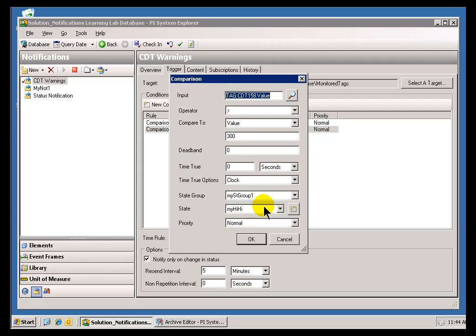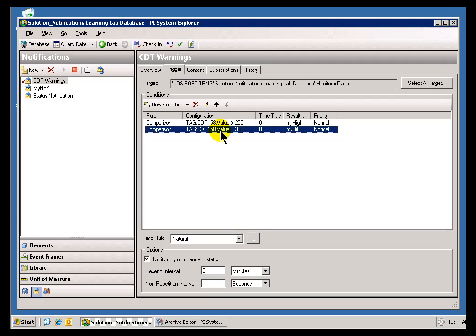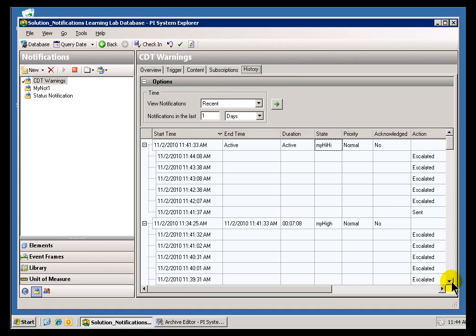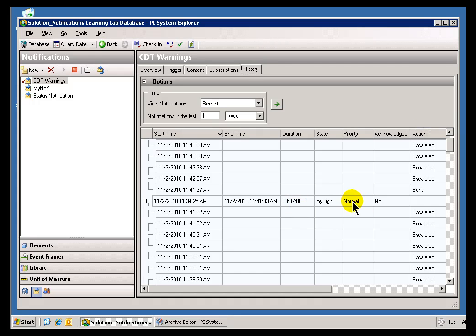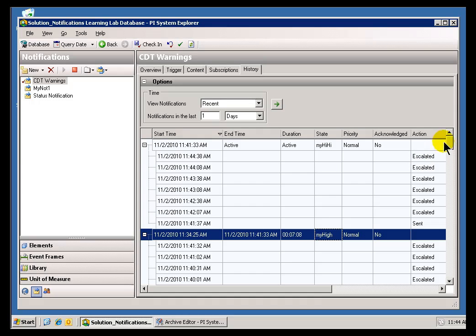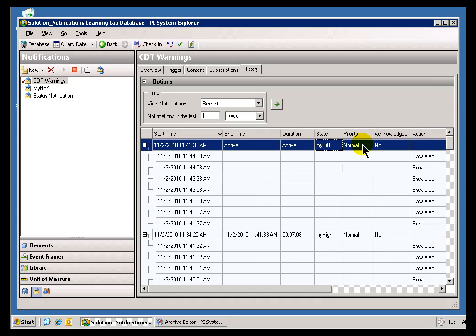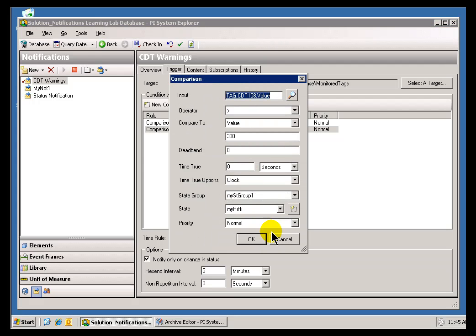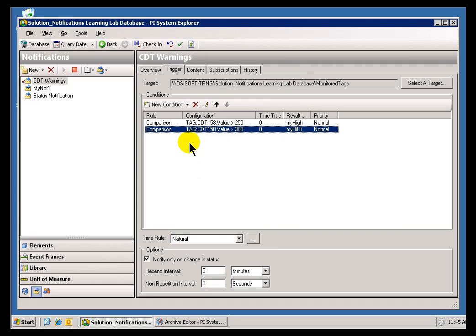Now if you look at this next one, when it's greater than 300, we're going to say that's a High High Alarm, or High High Notification — reflective of something in a more severe State. That's going to show up when you look at the History. I drove that Tag to 275, which should have violated the High Alarm, and then I drove it to 319, which should have made it past the High High Alarm — and in fact that's exactly what happened. This is one of those Escalated Notifications, sending over and over again until somebody acknowledges first the High Alarm, and then the High High Notification. So that's the effect of modifying this so that it sends different States depending on which condition triggers the Notification.